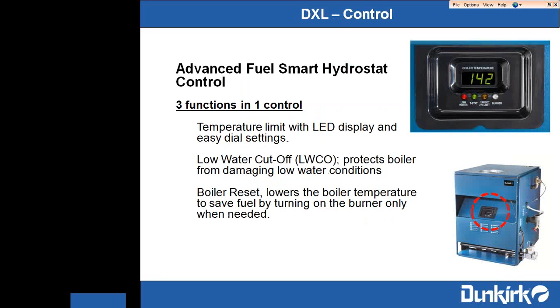So that's what the hydro-level hydrostat control looks like. Again, it's got a nice digital display for the contractor. Low-water cutoff is built in, and then the boiler reset control that we all needed to add to our boilers, both for hot water gas as well as hot water oil. It is on there. And again, what that simply does is delay ignition and try to satisfy a call for heat by circulating latent heated water that's within the boiler from the last run cycle.